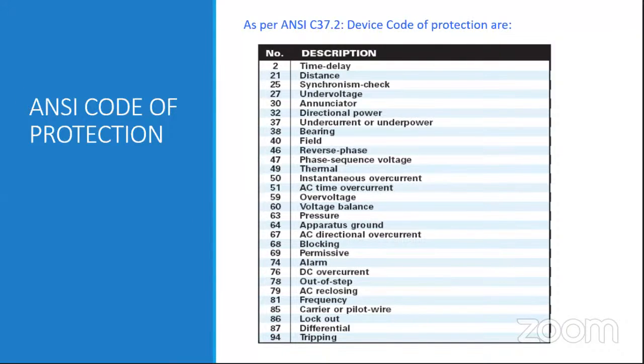67, AC directional overcurrent. As I said earlier, for directional power it's 32. 67 is for overcurrent protection. Directional overcurrent protection will detect the direction of the power, and accordingly, if there is a reverse flow of the power or the current, then it will detect it.